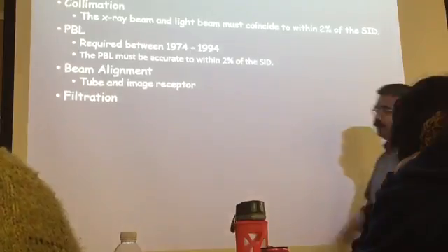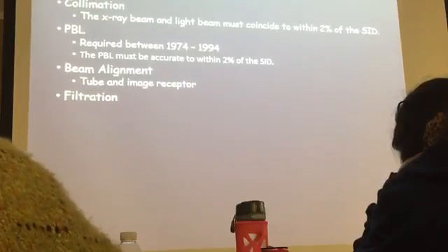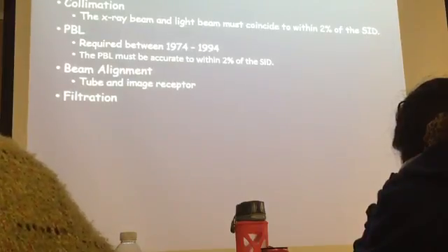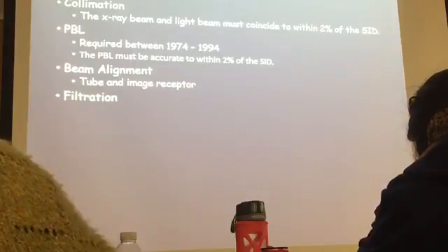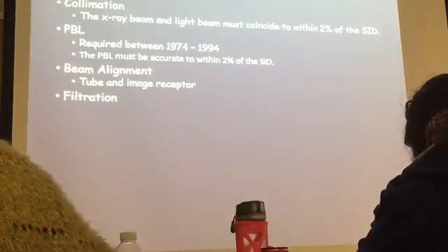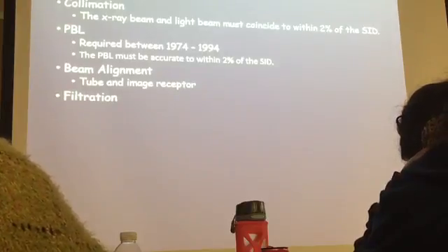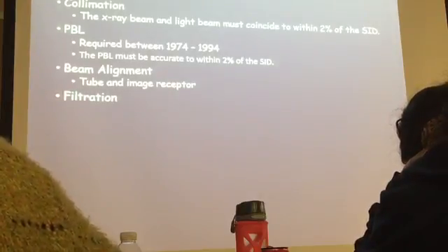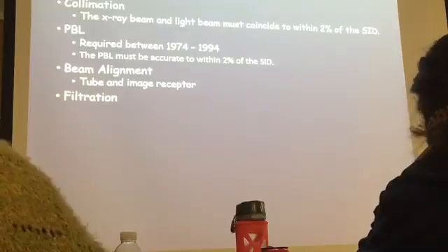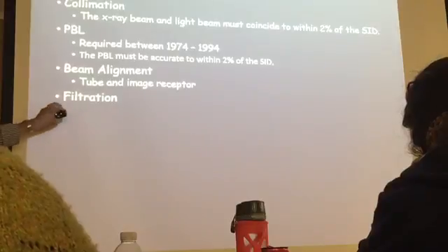Okay. Filtration, the purpose, as we have looked at in this class, is to absorb low energy photons coming out of the X-ray tubes. These photons are not going to help in creating an image. Make sense? All these photons are doing is exposing the tissues, exposing the skin, maybe the first centimeter of the skin. Why do you want to expose a patient if it's not going to help in creating the image? And so filtration is important.